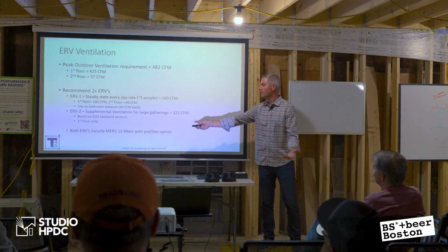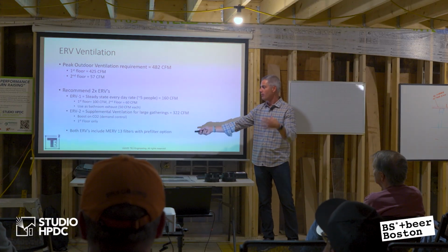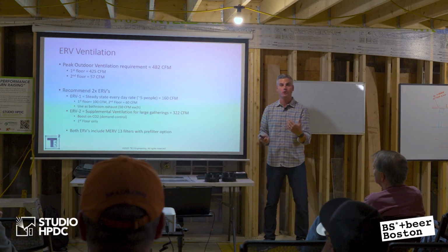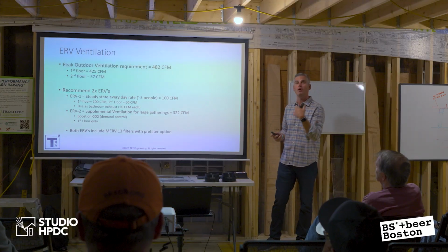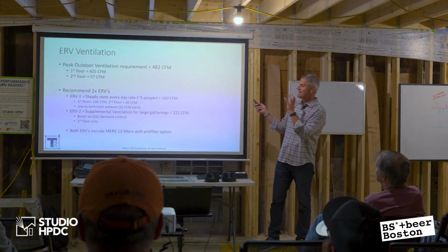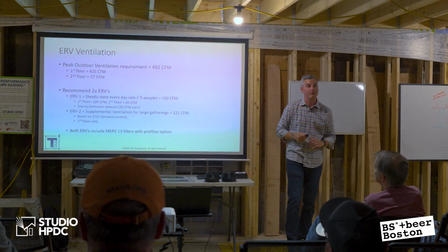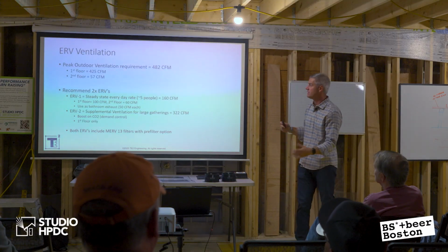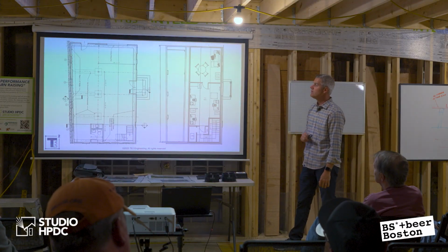So based on CO2, it would handle the first floor only. Okay? We could talk about MERV 13 filters. We could talk about pre-filters, right, for dealing with wildfire smoke and other issues and things like that. But just high level conceptually, that's what I would recommend for this building as an ERV strategy and ventilation strategy for it.